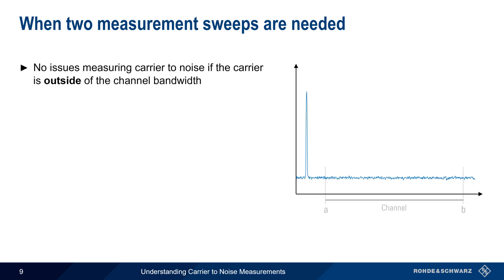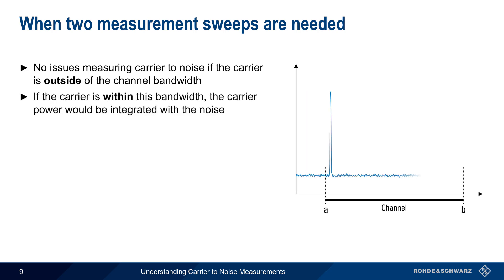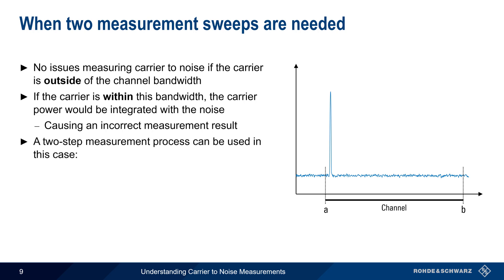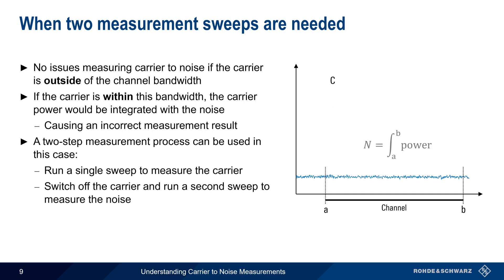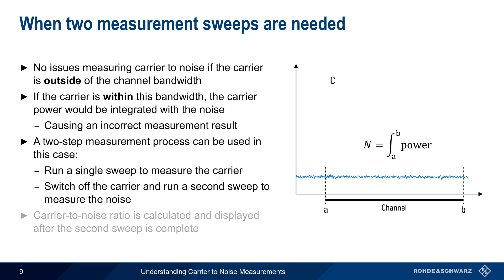If the carrier lies outside of the user-defined channel bandwidth, as shown here, only a single sweep is needed to measure both the carrier and the noise. However, if the carrier were within the channel bandwidth, the carrier power would be included when integrating over the channel, and the noise measurement result would be incorrectly high. In this case, a two-step measurement process is needed. First, a single sweep is run and the power in the carrier is measured. Then the carrier is switched off and a second sweep is run to measure the noise alone. In this way, the carrier-to-noise ratio can be calculated and displayed automatically by the spectrum analyzer after the second measurement sweep is complete.